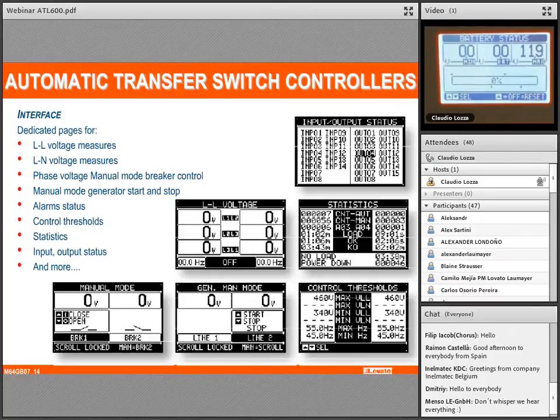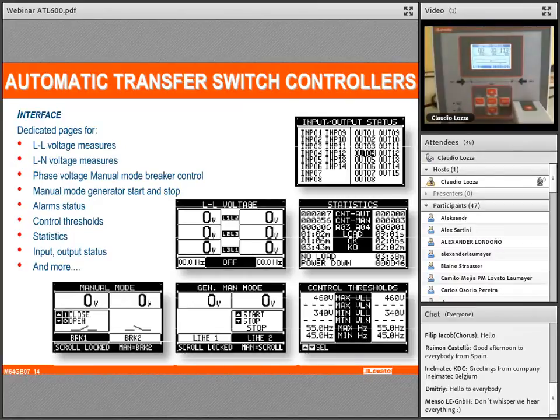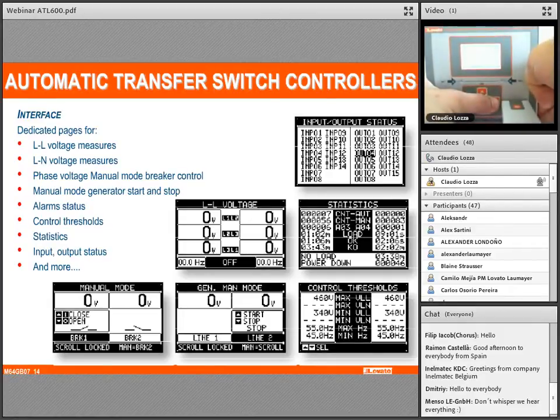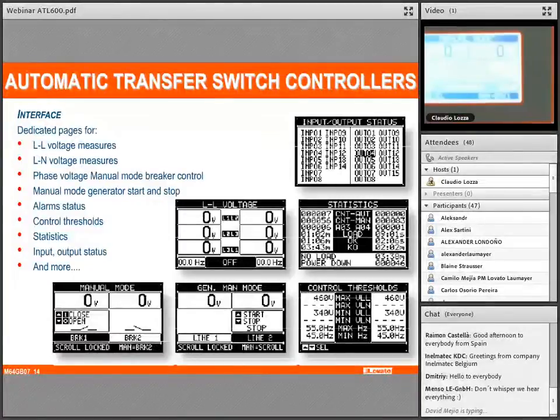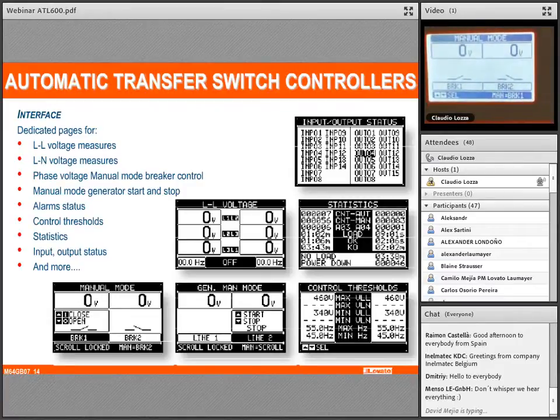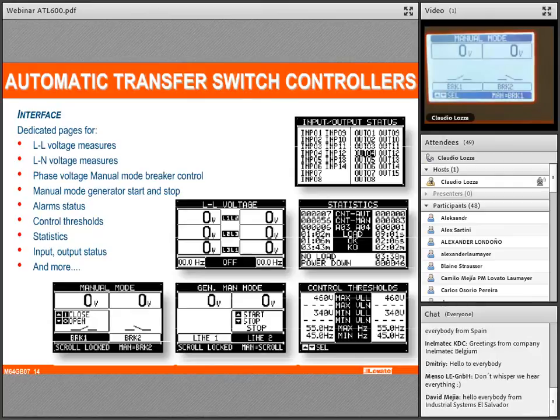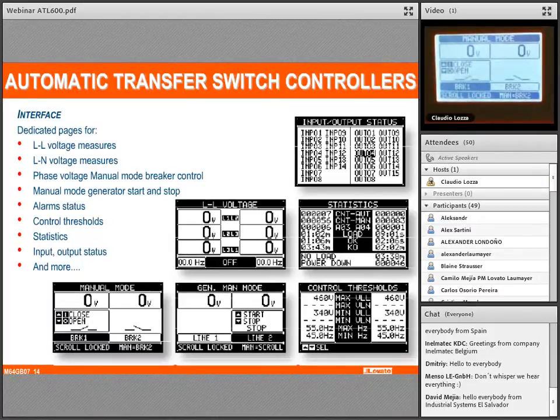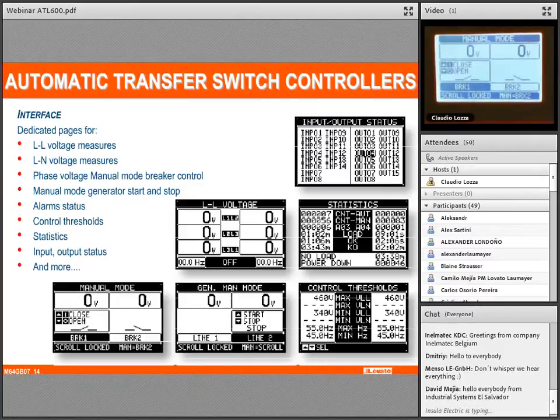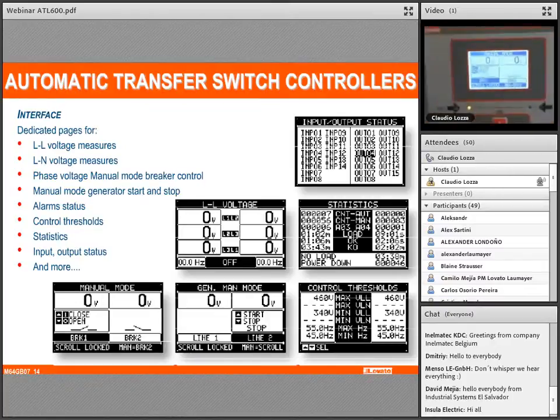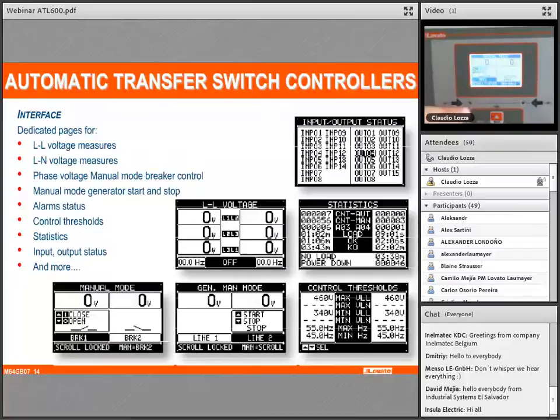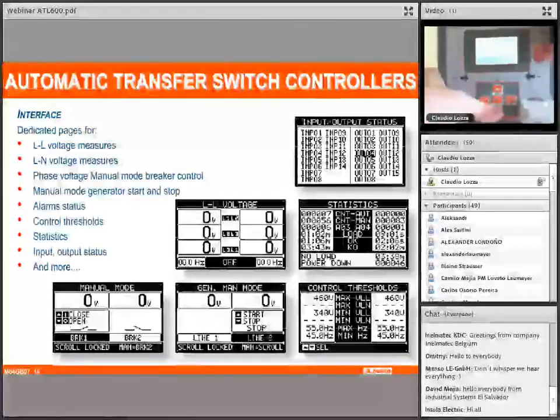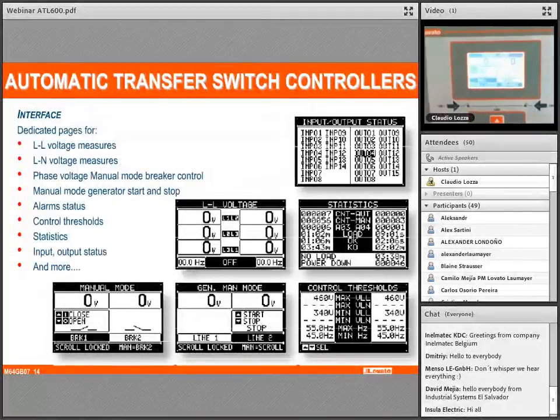Another important feature is the manual mode. For example, now I show you: when I press the MAN key, the page changes automatically, and on the display I have the two contacts, the contact for breaker 1 and the contact for breaker 2. Then, using the MAN key, I can select the breaker and then close or open the breaker. Now I show you the LED. You can see the LED flashing because I sent the command to close the breaker. Of course, now I open it and the LED stops flashing.